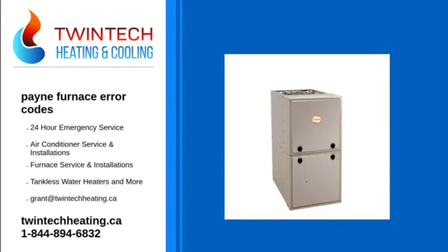Payne furnace error codes. The Payne gas furnace has built-in diagnostics and is designed to assist with the identification and correction of faults. The furnace utilizes an LED to describe its condition. This can be viewed through a port on the blower access panel. You can take corrective action in response to any faults indicated by the LED.